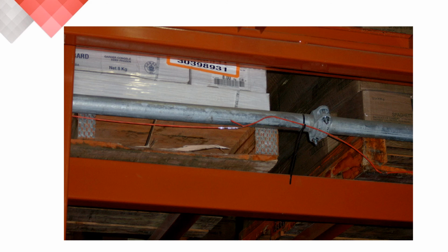With a pre-action or double interlock pre-action system, we're looking for 2 things to happen: an alarm from your initiating device as well as a low air condition in your pipes. If a pallet falls out of a rack and damages the sprinkler piping as well as hits the standard Protectowire, you could have both conditions necessary to put water into those pipes.